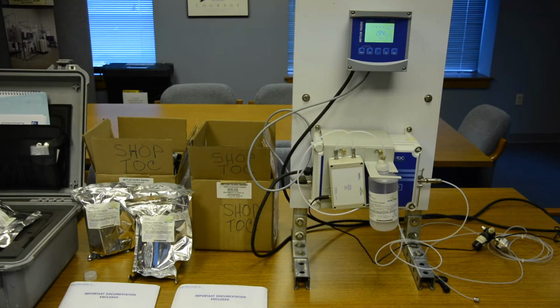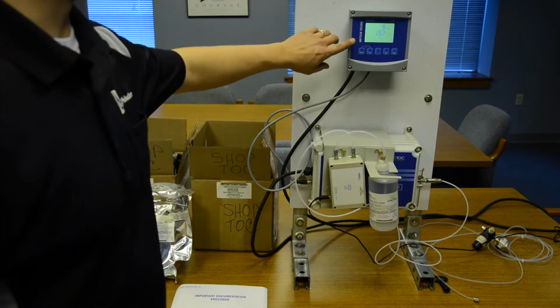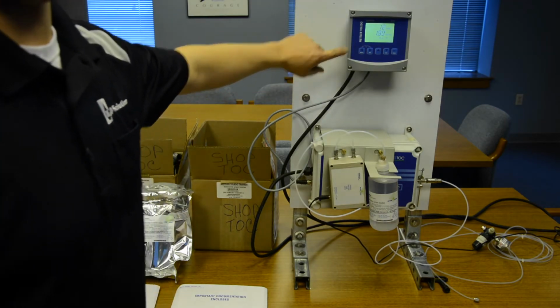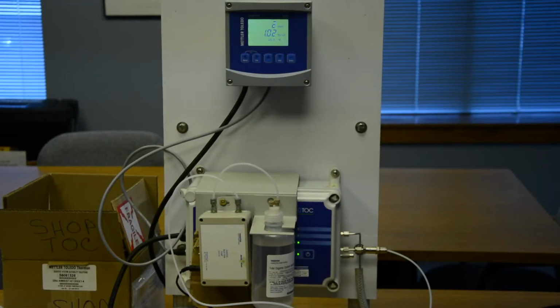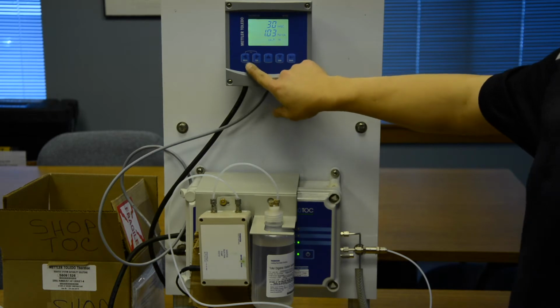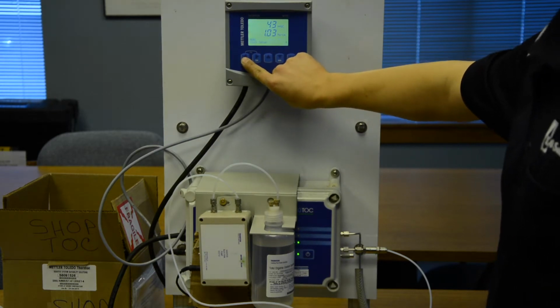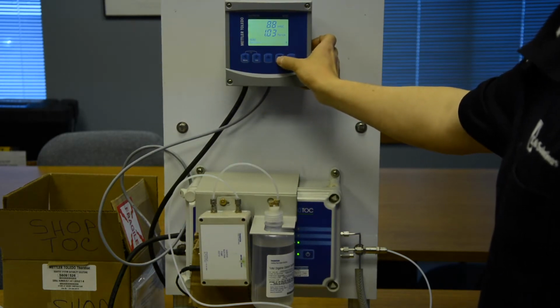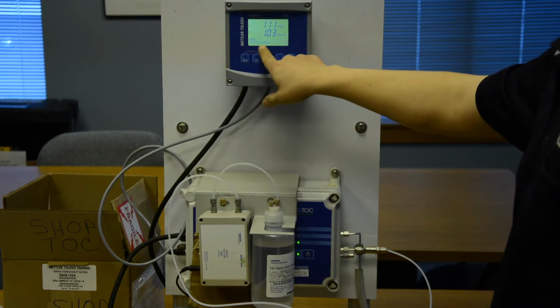Make sure that you have proper flow and set up your flow inside of your M300. I will show you how to do that next. With the injection pump on, go into your M300 unit, go into menu, scroll down until you see set flow rate.